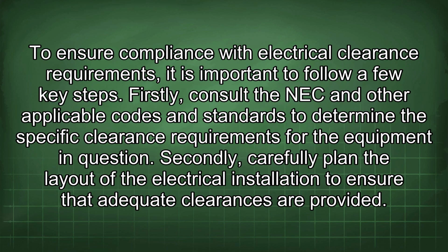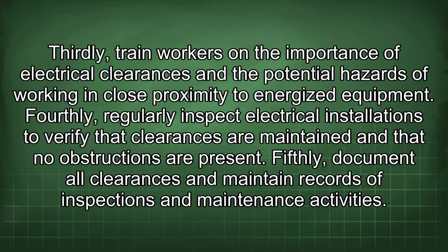To ensure compliance with electrical clearance requirements, it is important to follow a few key steps. Firstly, consult the NEC and other applicable codes and standards to determine the specific clearance requirements for the equipment in question. Secondly, carefully plan the layout of the electrical installation to ensure that adequate clearances are provided. Thirdly, train workers on the importance of electrical clearances and the potential hazards of working in close proximity to energized equipment. Fourthly, regularly inspect electrical installations to verify that clearances are maintained and that no obstructions are present. Fifthly, document all clearances and maintain records of inspections and maintenance activities.